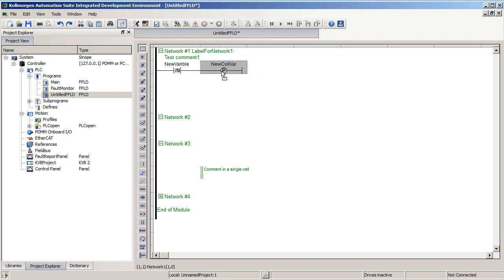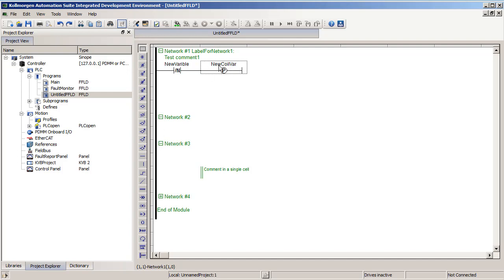We also have the P, or pulse coil, just similar to the pulse contact. When power flows through it on the rising edge, when power first flows through it, it will make the containing variable true. But otherwise it will stay false.